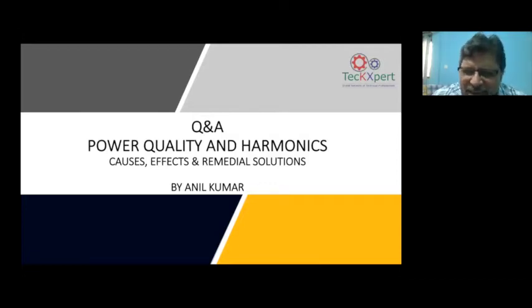So that means 3% losses on the active harmonic filter is also energy loss. So that means better technology active harmonic filter, and see how much is the harmonic level in the network, see what is the power factor in the network, what is the size of the network, what is the wattage losses in the network, and then you can calculate the return on investment. It is possible, I would say.